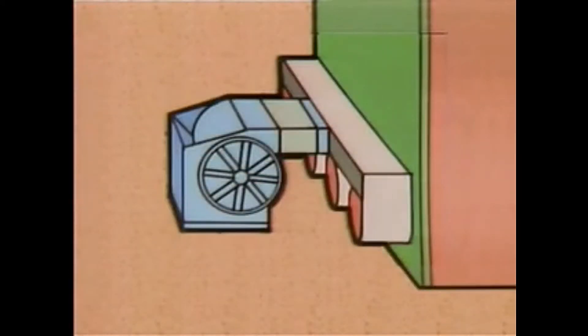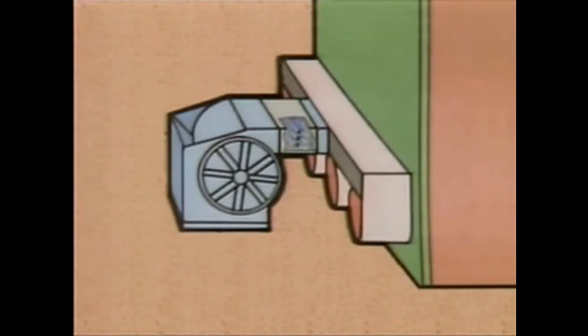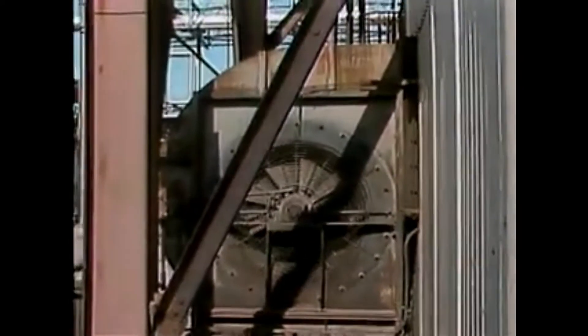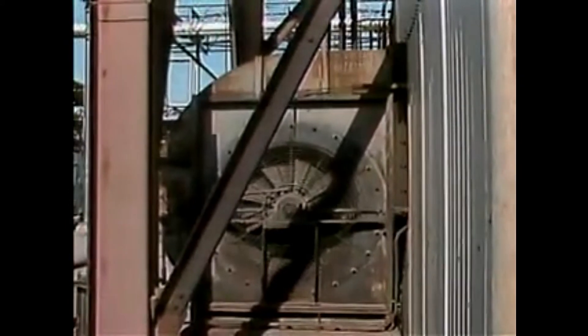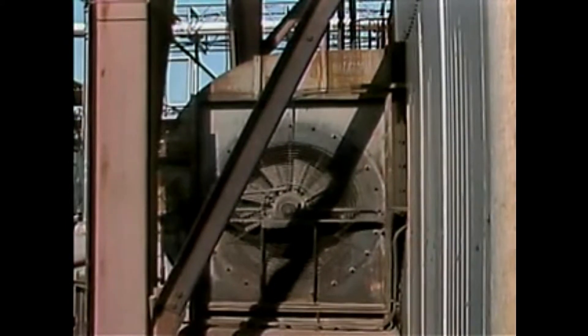Some force draft fans have dampers or louvers on the discharge side of the fan. These dampers can be opened or closed to allow more or less air to flow into the furnace. On other types of force draft fans, the dampers are located on the inlet side. Adjusting the inlet dampers increases or decreases the amount of air that is admitted to the fan and into the furnace.